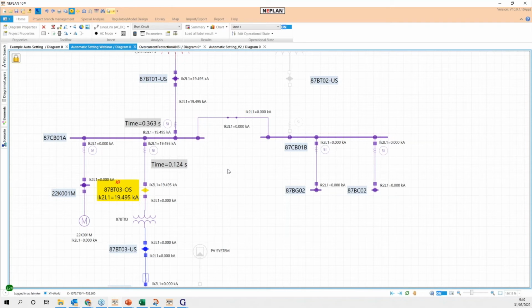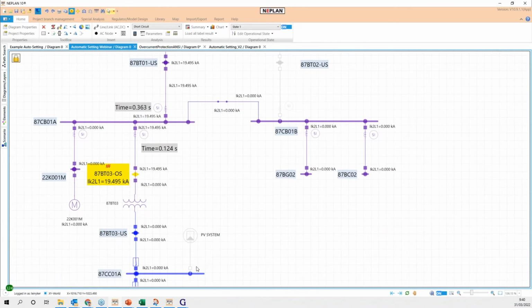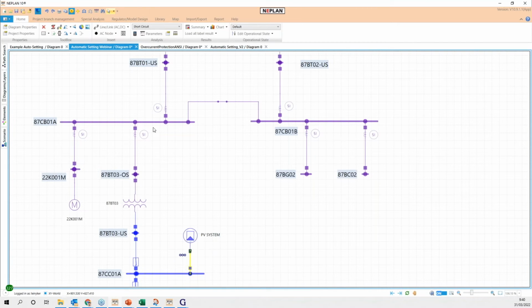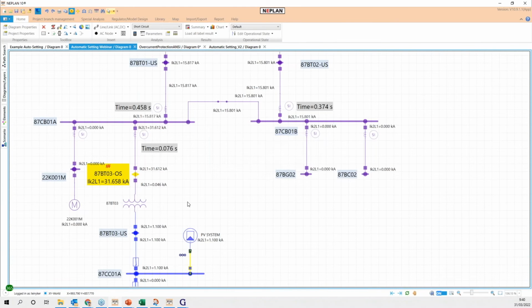So this is the example for the setting criteria. And for sure, the same impact if we connect or disconnect the distributed generator. So NEPLAN allows to get the different settings for the different topologies. So write to my email. I will give you my email if you would like to see what is the solution once we change the topology when we connect the distributed generator in order to give the proper selectivity for the whole system.